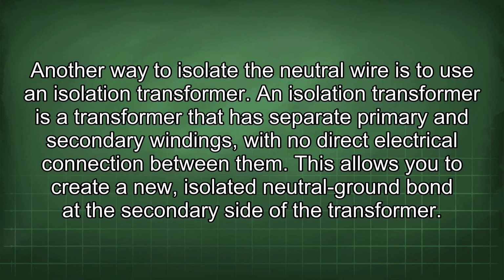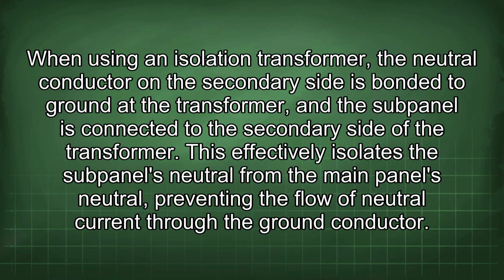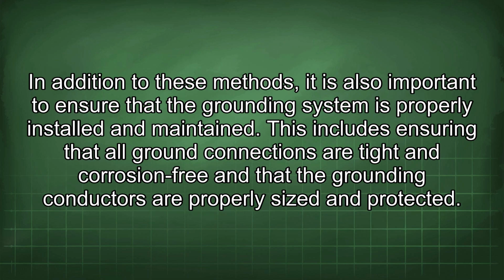This allows you to create a new, isolated neutral ground bond at the secondary side of the transformer. When using an isolation transformer, the neutral conductor on the secondary side is bonded to ground at the transformer, and the subpanel is connected to the secondary side of the transformer. This effectively isolates the subpanel's neutral from the main panel's neutral, preventing the flow of neutral current through the ground conductor.